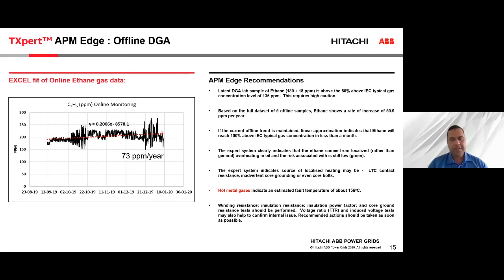So the expert system clearly indicated that ethane is coming from a localized heating source rather than an overall heating of the transformer. We calculated the hot metal gases, what is the likely temperature, and we recommended what tests we need to do to figure out what has gone wrong.